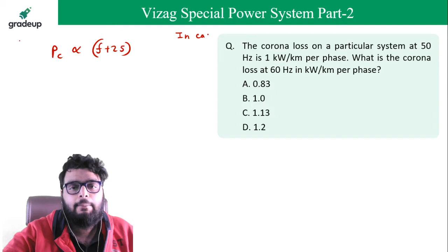In case of DC, first I will tell you about DC. In case of DC, frequency becomes 0, so corona loss is proportional to 25. It means corona loss is not going to be 0. So remember this point: there will be a corona loss in case of DC, but the magnitude as compared to AC will be less, because if you increase the frequency, the corona loss will increase. Got my point? Now come back to this question.